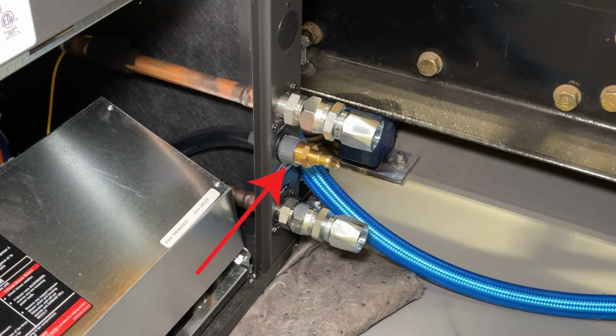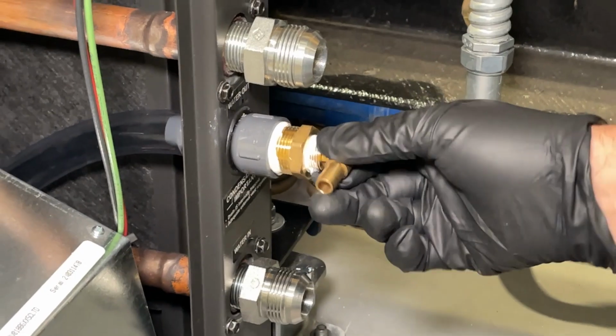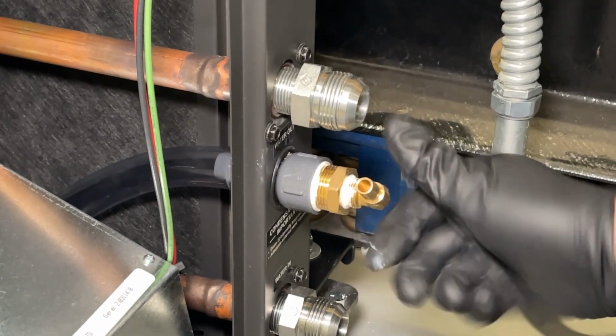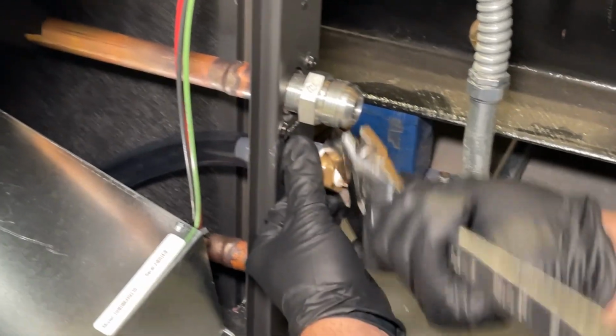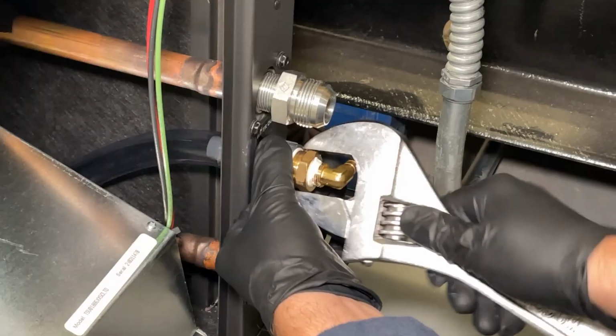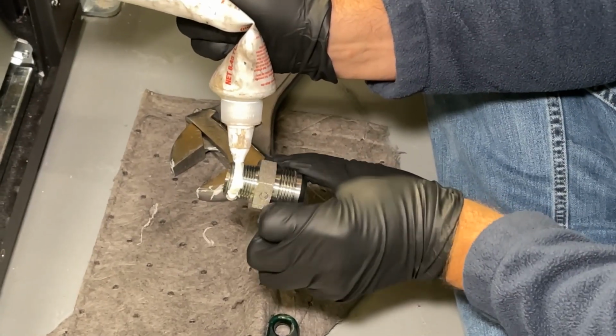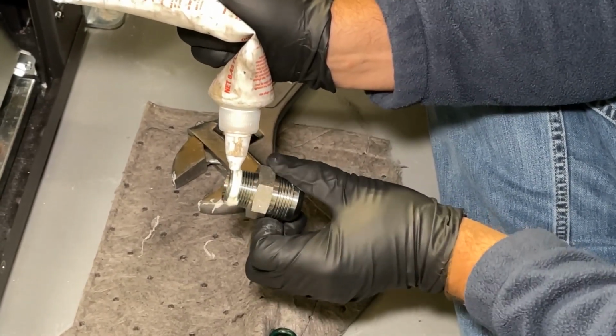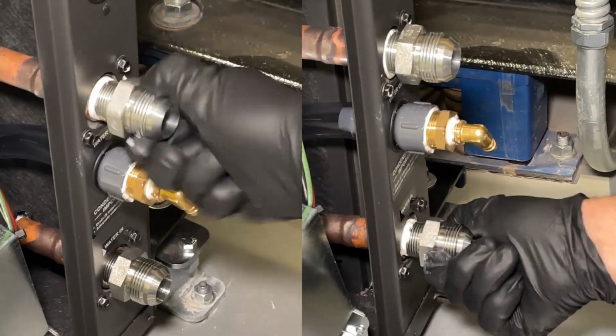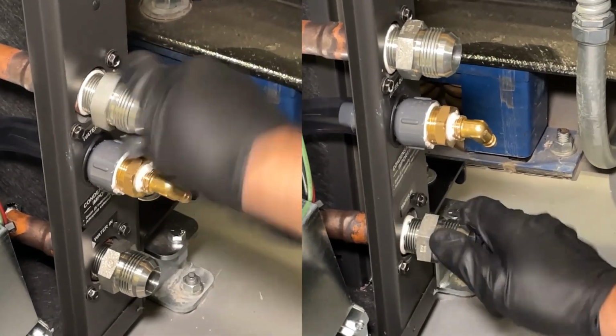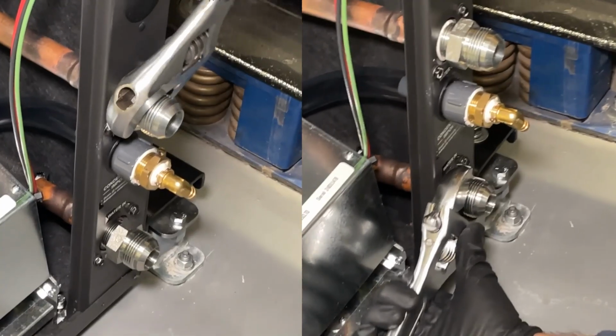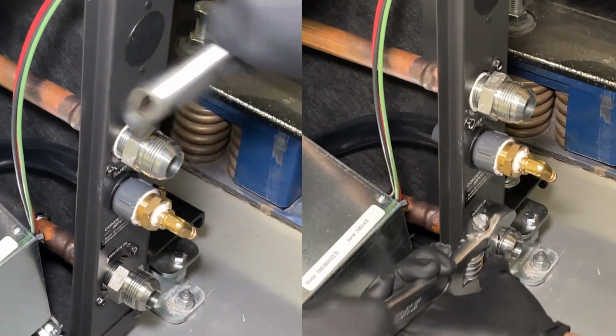Locate the condensate port on the front of the HE between the coolant in and coolant out ports. Hand tighten a 3/4 inch fitting to the port, then secure with a wrench. Use pipe joint compound on metal fittings. Avoid getting compound in the coolant port and plumbing. Hand tighten the fittings in the ports, then secure them in place with a wrench.